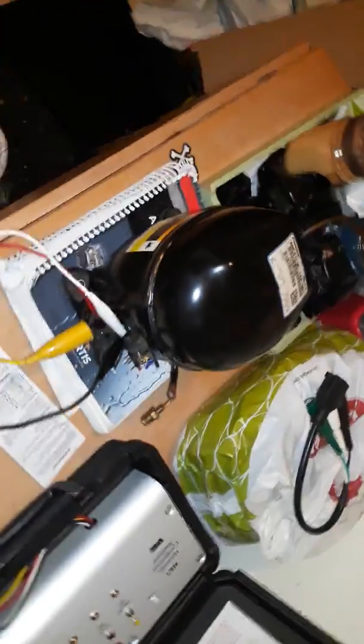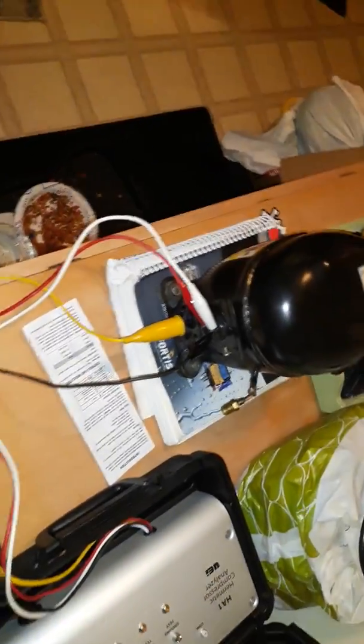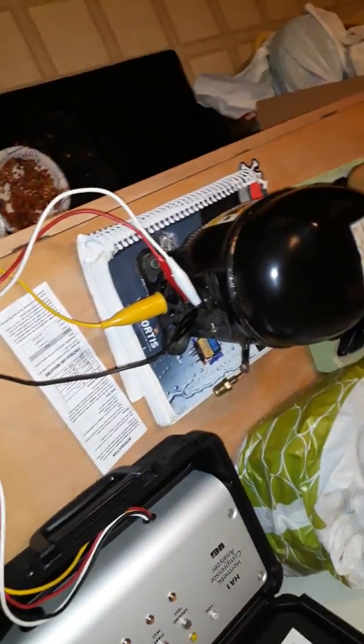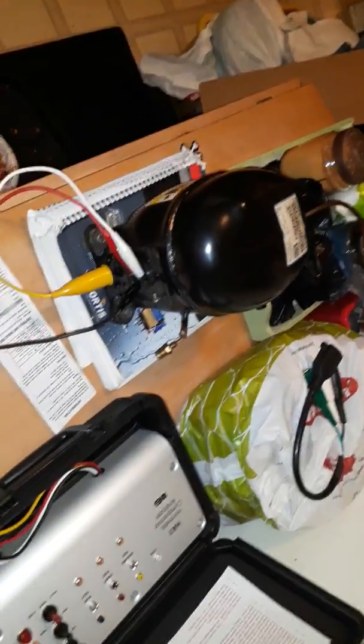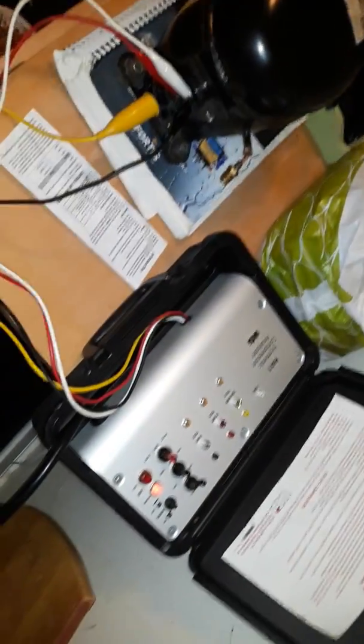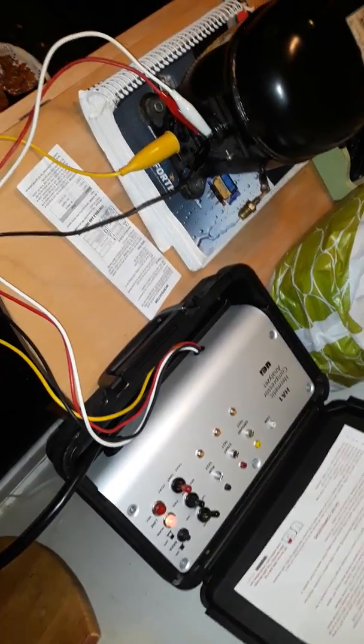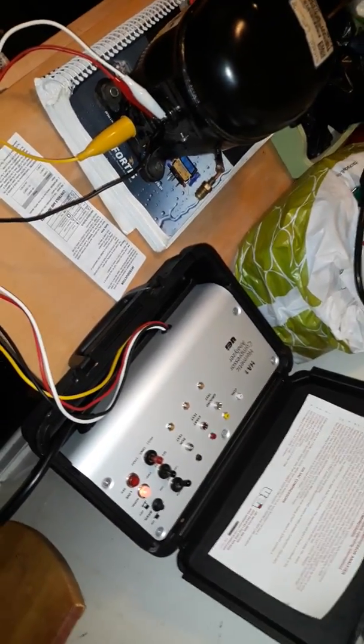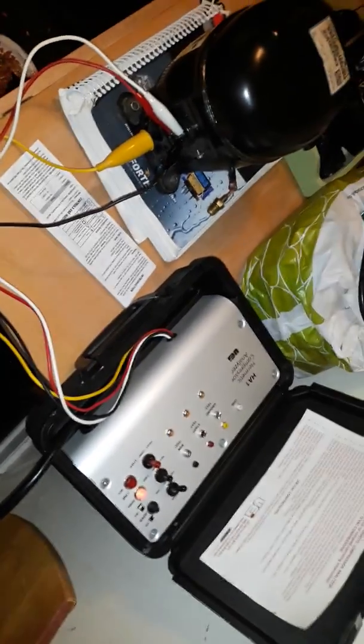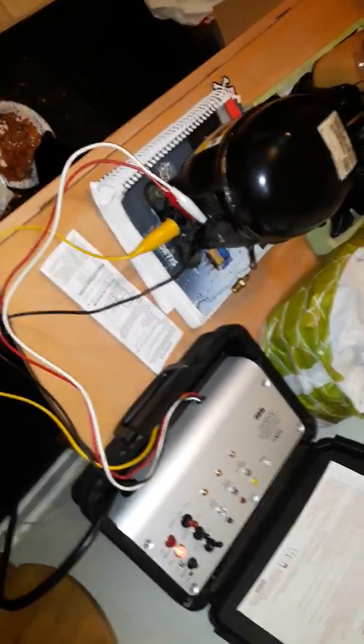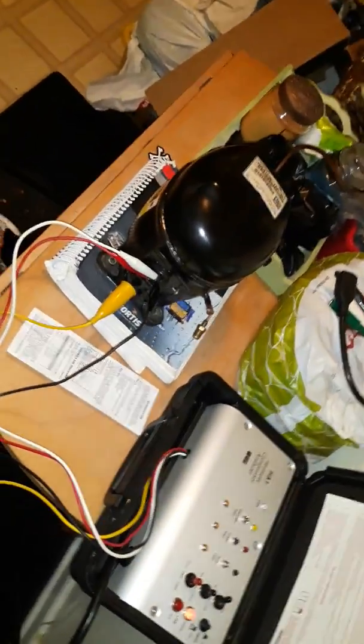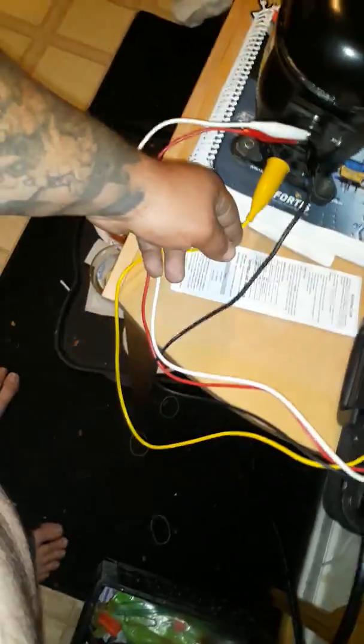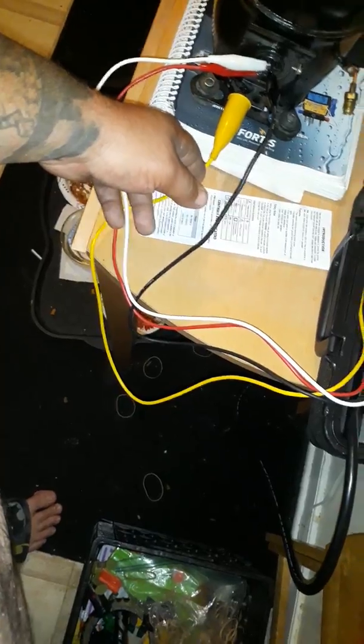I had continuity between all three legs there on the peckerhead. So anyway, I ended up buying this thing so that I don't have to put any more guesswork into whether a filter dryer is clogged up or if there's a cap tube restriction or anything like that.